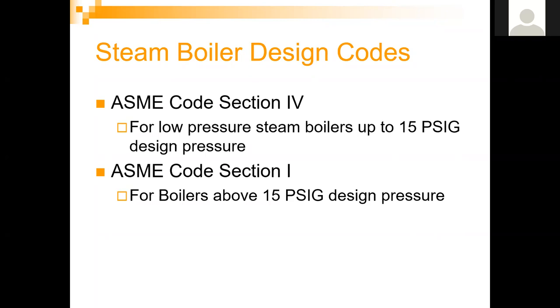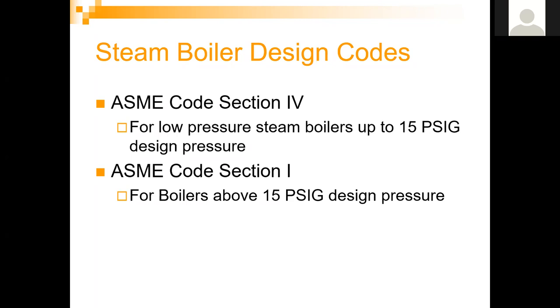ASME Code Section 1 is for all steam boilers above that design pressure. It's much more stringent on the NDE — non-destructive examination — required, including x-raying of welds and other non-destructive examination, as well as all the boiler valves and other codes. Anything with a relief valve set point or design pressure above 15 PSI falls into ASME Code Section 1 of the pressure vessel code.